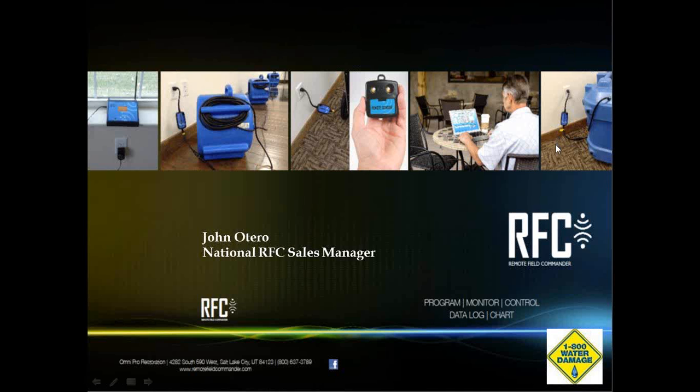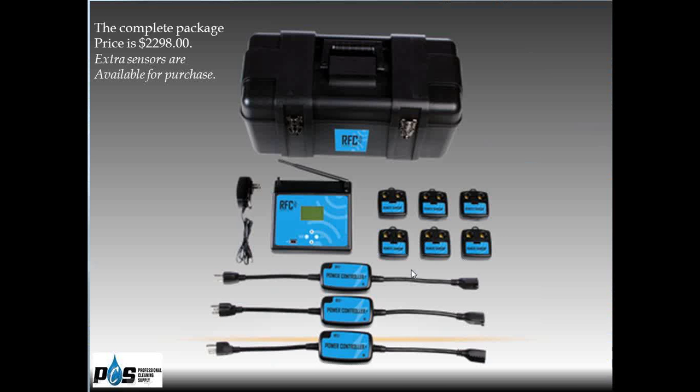One of Doug's questions is, I'm not sure how it reads moisture content in wood. And it does. I'll show you real quick here. Let's see if I can get this going. So, Doug, there are holes in these sensors. And what you do is drive uncoated screws through these holes into the sill plate or the subfloor or the drywall. The screws create conductivity. And the sensors have readings in there, and that will read the moisture content from the screws themselves.